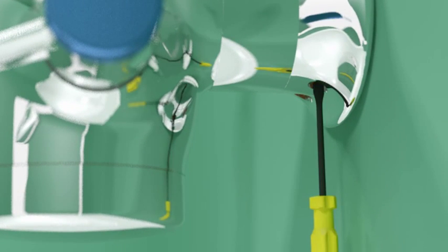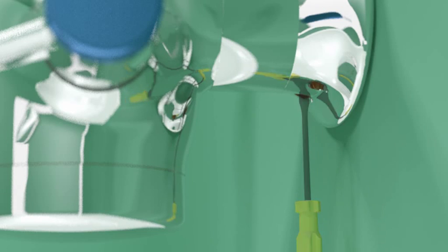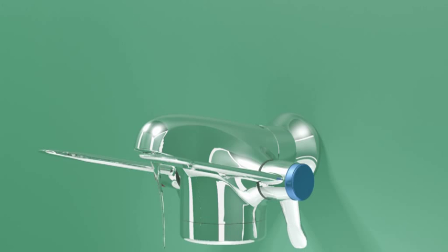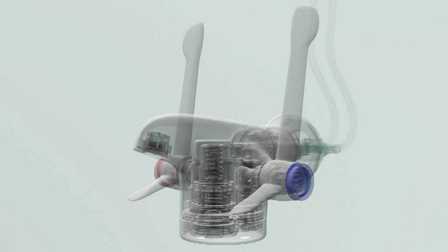Isolate the hot and cold water supplies by means of the integral ball valves accessed underneath the tap spigot. Open the levers and allow residual water to drain. Remove the tap's bottom cover using a strap wrench.